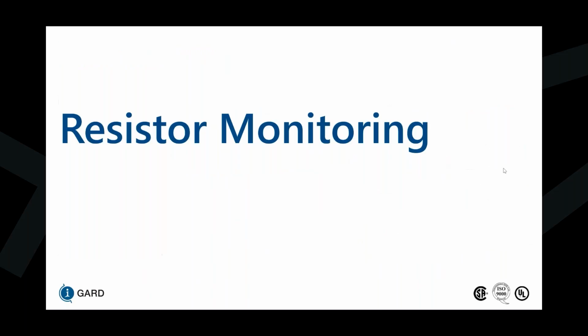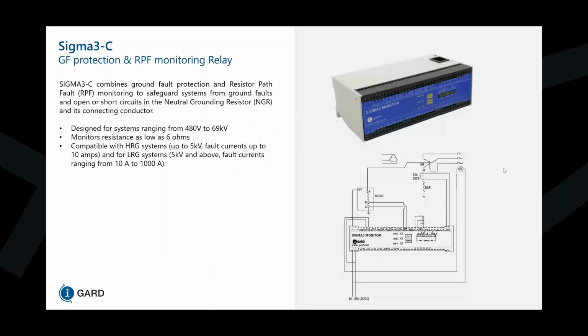Now, resistor monitoring, we have our Sigma 3C relay here. It combines ground fault protection and resistor path fault monitoring to safeguard systems from ground faults and open or short circuits in the neutral grounding resistor and its connecting conductor. So instead of just monitoring the NGR, we're actually monitoring the entire path between XO and ground in an effort to pick up any open or short circuit conditions throughout that entire path. That's why we switched to resistor path fault monitoring rather than just NGR monitoring.